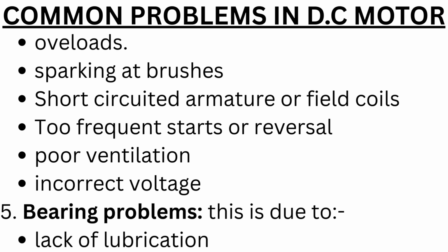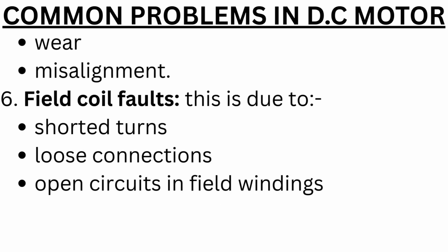5. Bearing problems. This is due to lack of lubrication, wear, misalignment. 6. Field coil faults. This is due to shorted turns, loose connections, open circuits in field windings.